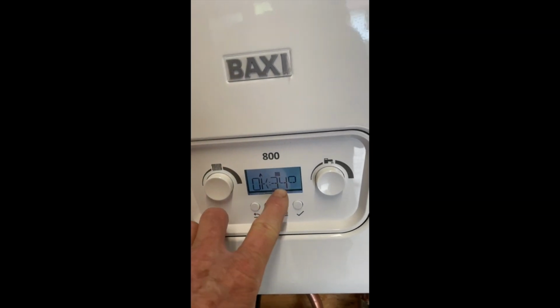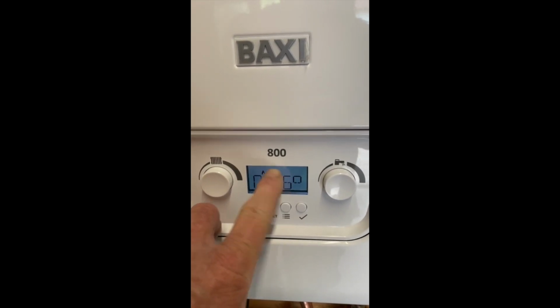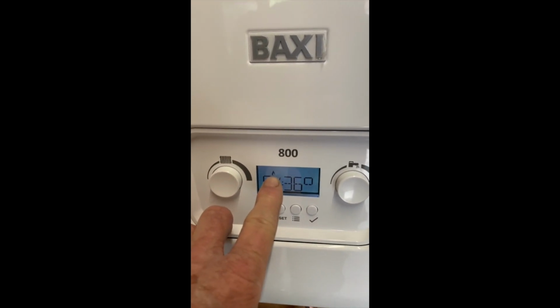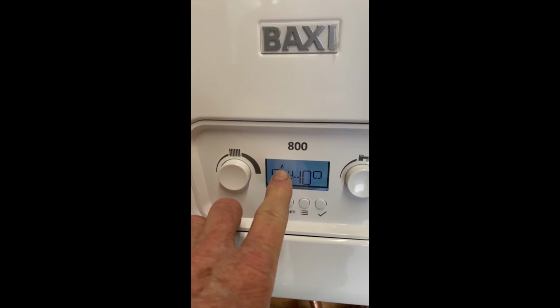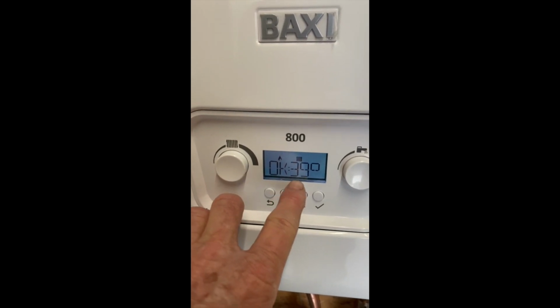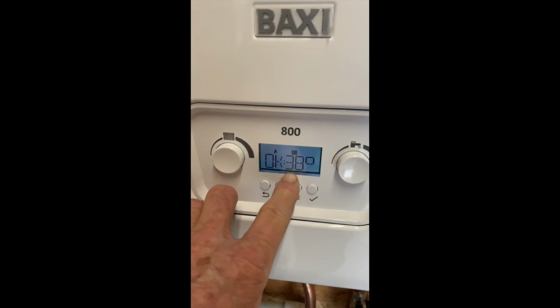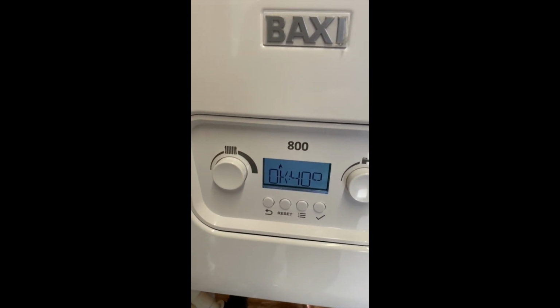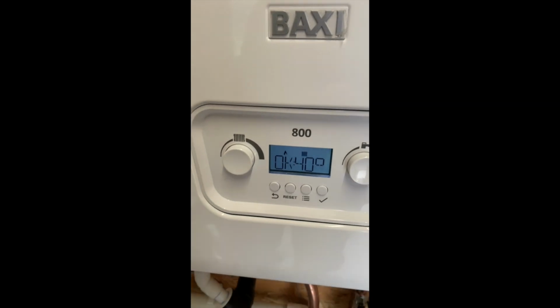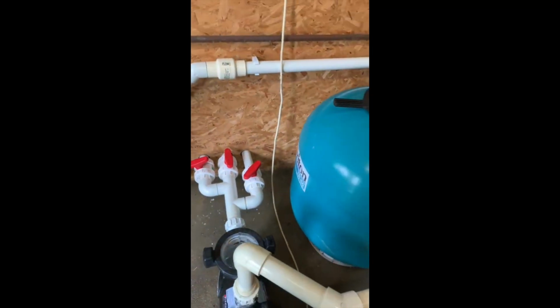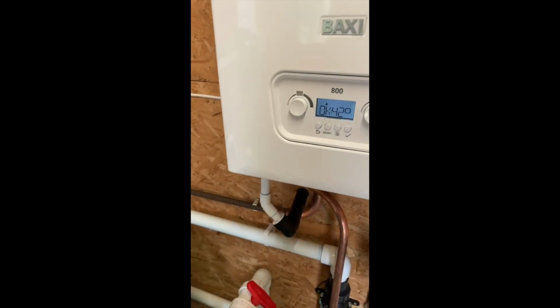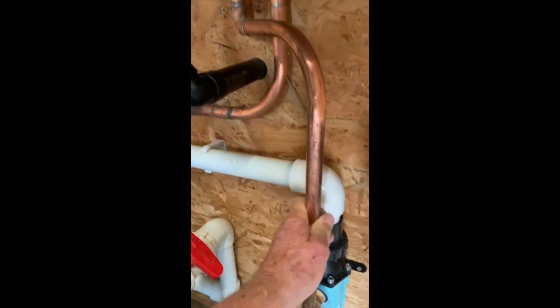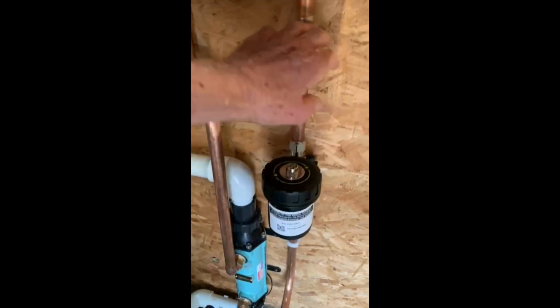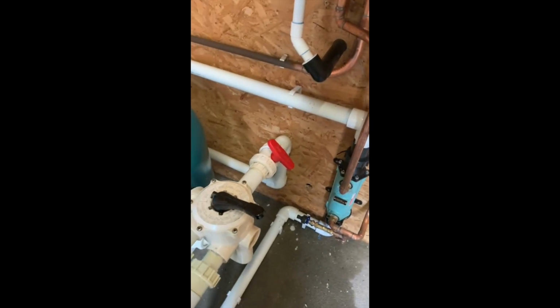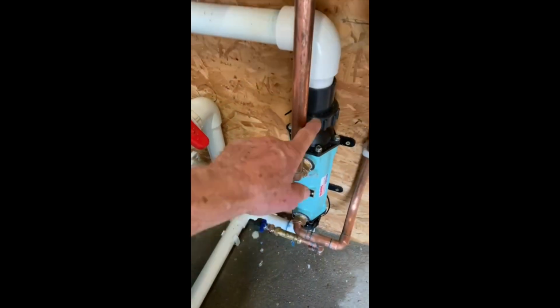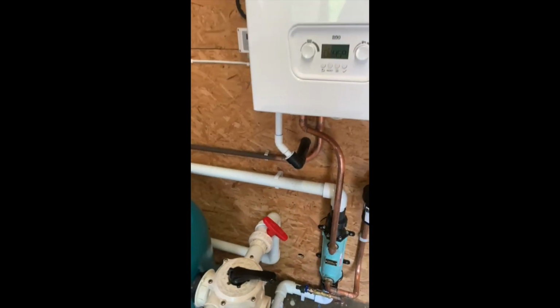Come back to the boiler now. You'll see that the boiler is showing the internal working temperature, and you've got the radiator flashing, which means there is a demand. You've just seen the light here, which is the gas light, lets you know the boiler is actually now firing. And then what will happen is this temperature will begin to rise fairly steadily. Just give that a moment, there you go, 40 degrees. So at which point I'm now going to turn on the circulation pump, otherwise the boiler is going to get quite hot quite quickly. So what's actually happening, we've got hot water coming out of the boiler here, going through the heat exchanger down there, going back up into the boiler there, and conversely the pool water is coming in the bottom pipe there, coming up the heat exchanger in the opposite direction and back out into the pool. And it's as simple as that.